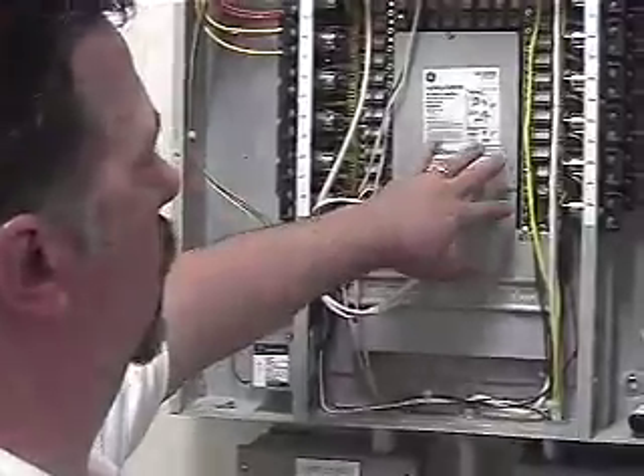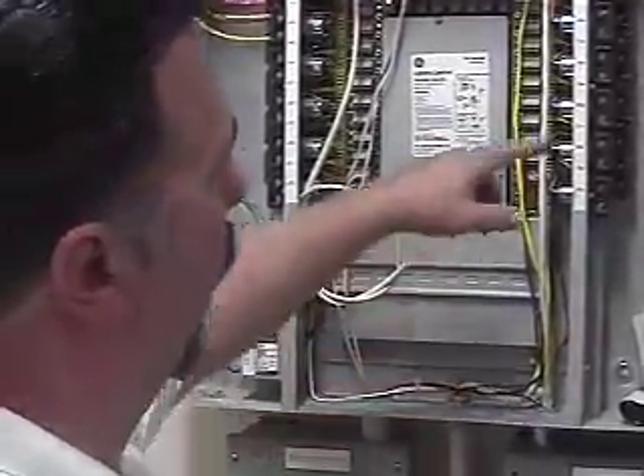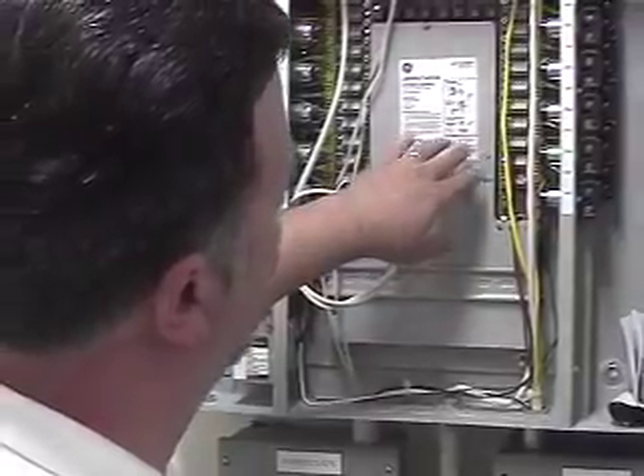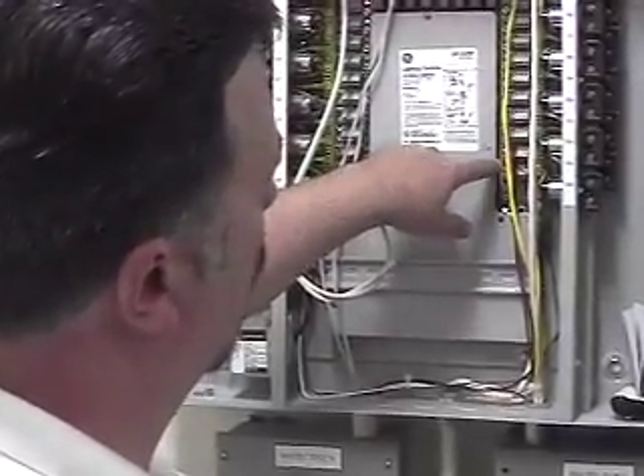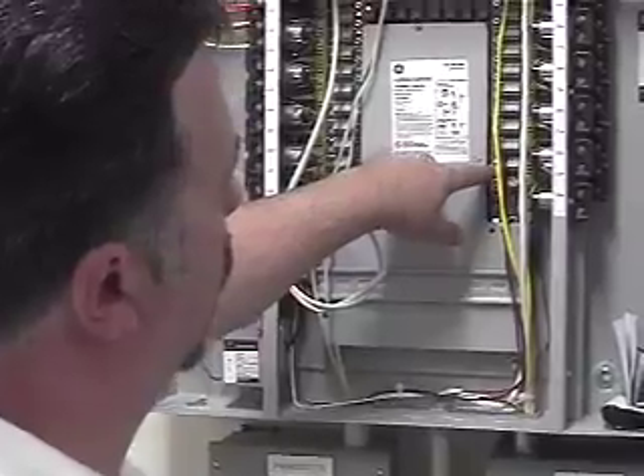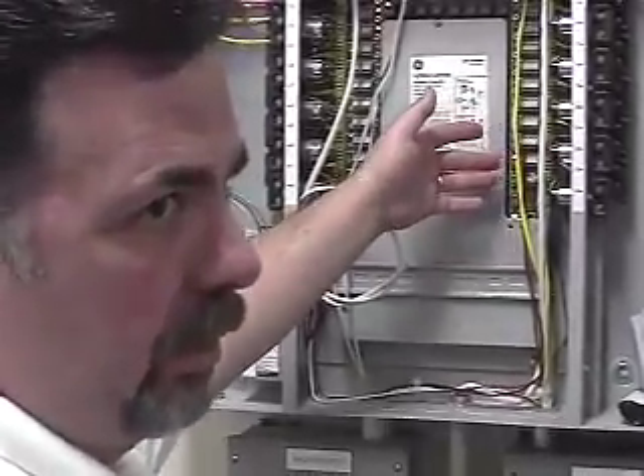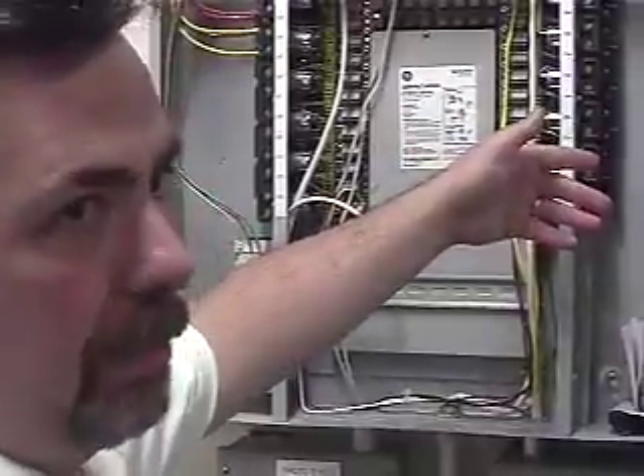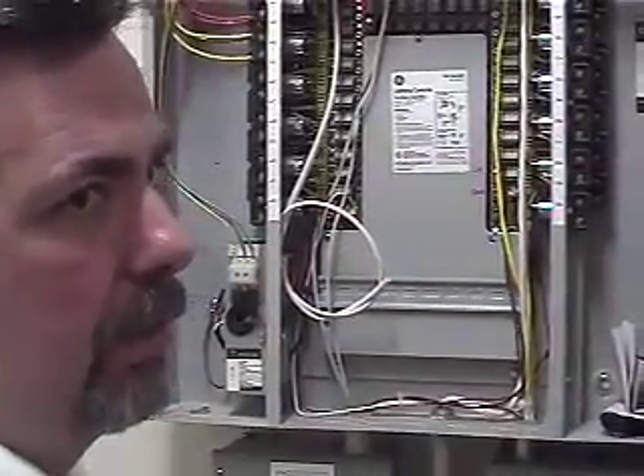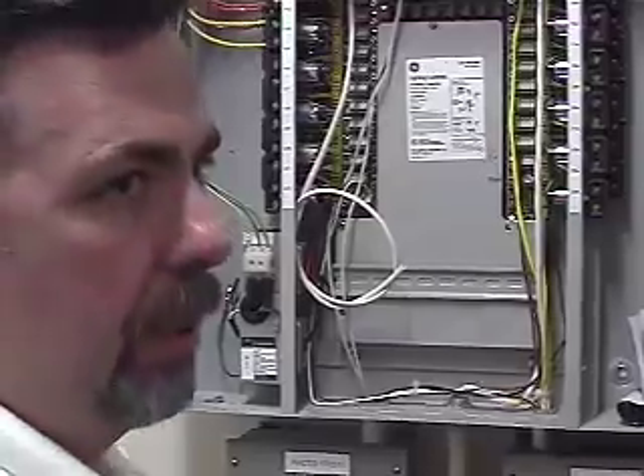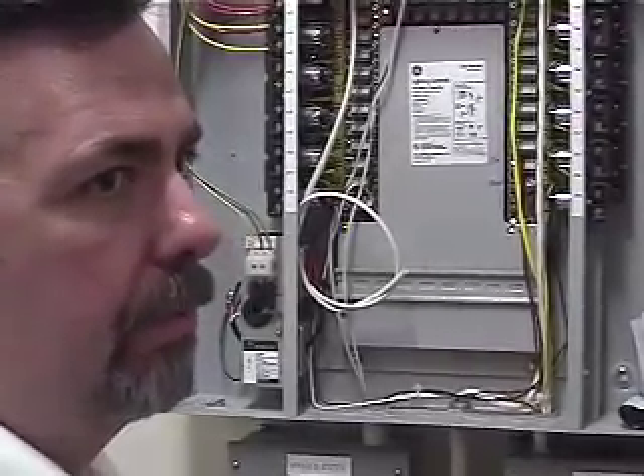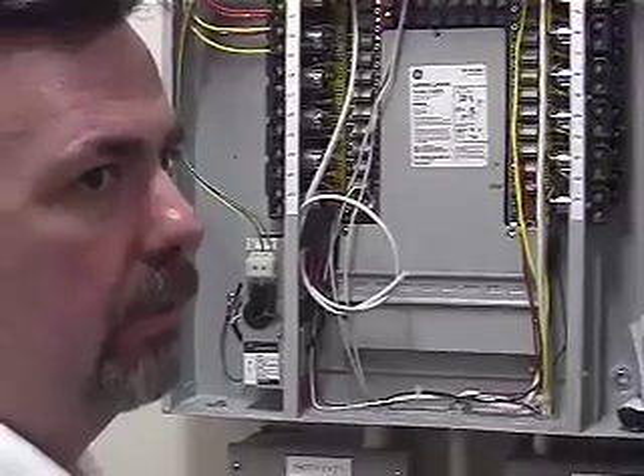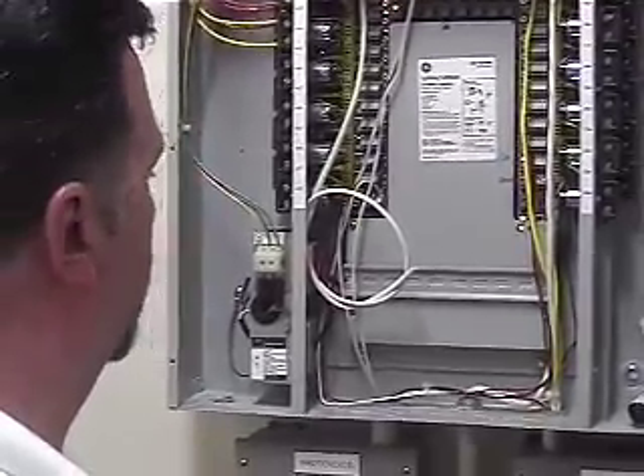So we monitor these relay outputs, and when these relays are turned on by what would be pretty much like a light switch turning it on, then we see that output turn on, and we know that that photocell is enabled. Because they're a pulse on, pulse off type contactor on the photocell. So there's an actual lens or something out here that's receiving the light. Right. So that goes back to those.